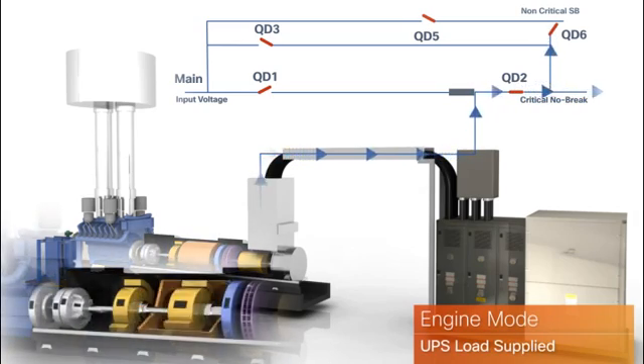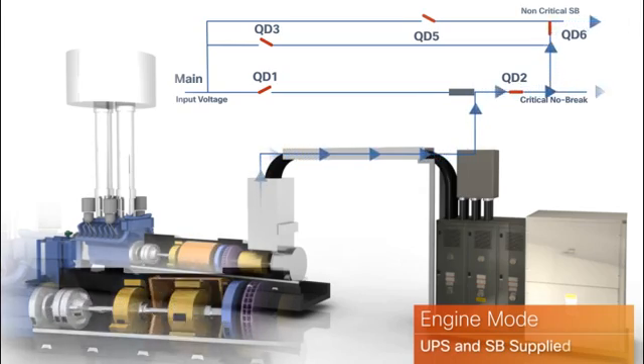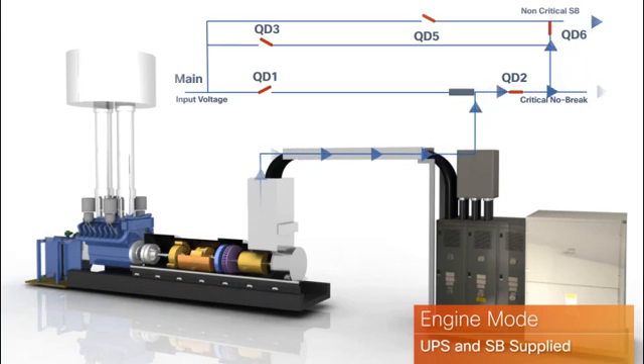If the outage lasts more than a few seconds, the diesel engine starts and the generator's electromagnetic clutch engages. The generator will continue to provide uninterruptible power to the IT loads.